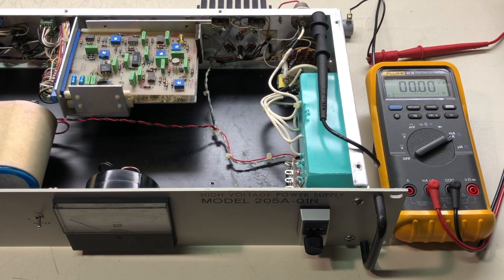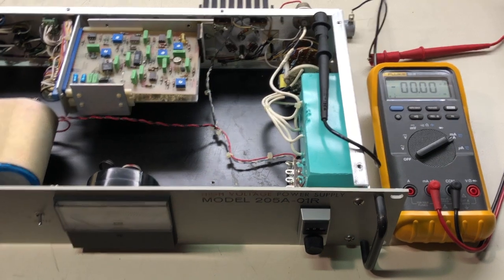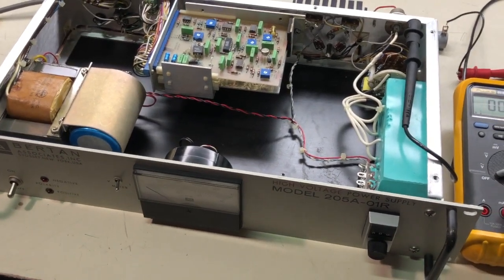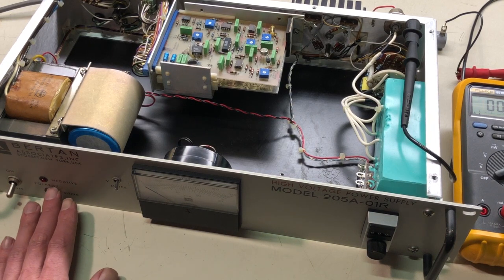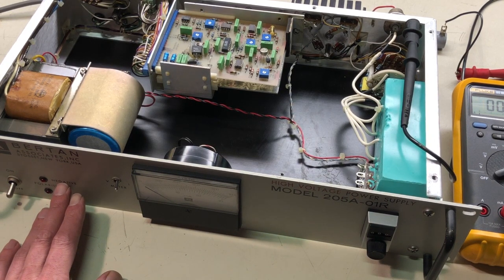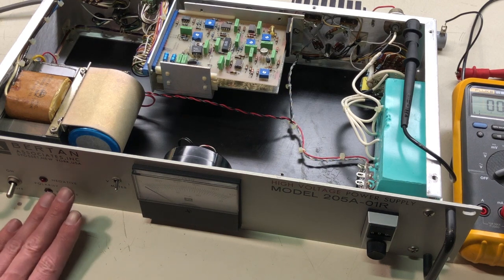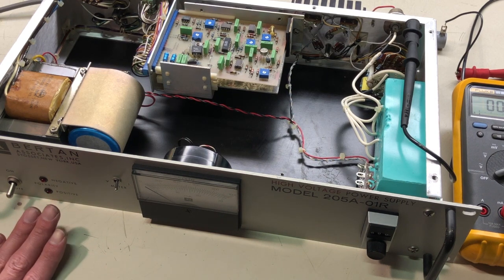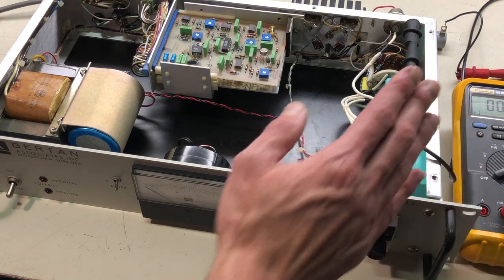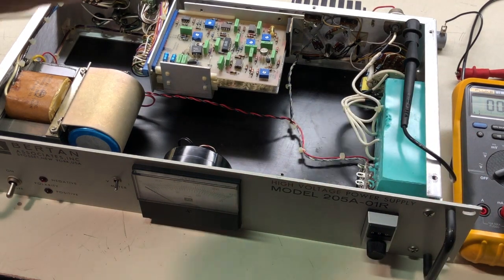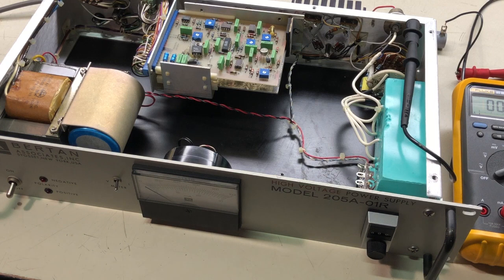So the one final test or check that I want to make on the power supply is that polarity switch on the back. We've been doing all the tests with this indicator, and you move the camera over a little bit here. This indicator has been on positive for the polarity on the output, but I want to make sure that the negative output is working correctly. Now the negative output, if I'm understanding correctly, I believe it should just be switching so that basically the main high voltage lead becomes negative in relation to the chassis. And that's easy to check on the multimeter. We'll just look for a negative voltage indication, so we'll do that test next.